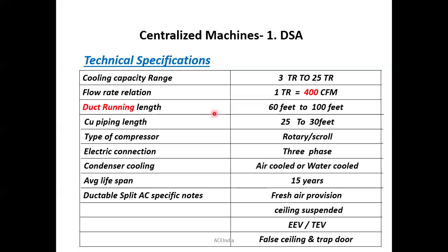Now we can study the technical specification of a DSC, which is a ductable split AC. Generally, these kinds of DSCs can be purchased in a capacity range of 3 ton to 25 ton. Okay, that is the normal capacity. And the other one, in the case of non-centralized systems, we studied that for 1 ton capacity it can provide up to 300 to 350 CFM of air, isn't it? But in the case of centralized machines, for 1 ton capacity, it can provide nearly 400 to 450 CFM.